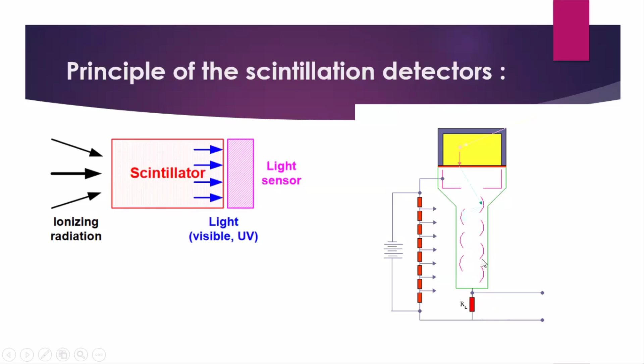So you have an ionizing radiation, and a sodium iodide crystal is there. As soon as the radiation falls on this sodium iodide crystal, photons will be generated, which will be detected by the light sensor, and then sent to the PMT. The PMT is again a tube, a kind of device only. We will not detail it, but it will multiply the photons. Right? So the photomultiplier tube will do the multiplication, and at the output you will get the photons in the form of a current, which will then be analyzed.